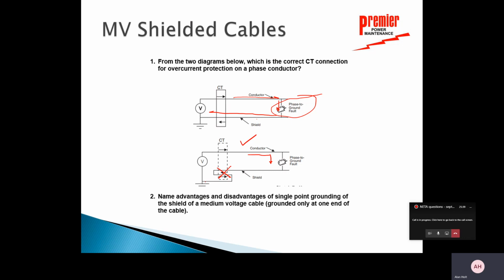Since there's no shield current, derating the cable ampacity is not a consideration. So I can actually look at the conductor size in the cable itself, and that's good. And the shield is useful in reducing noise and those sorts of things. So that's good. The disadvantage of having only a single point ground is that shield current cannot flow. If there's an open circuit voltage at one end and it's not grounded, that could be an issue. It does not provide protection against inductively induced noise, so that would be a disadvantage.